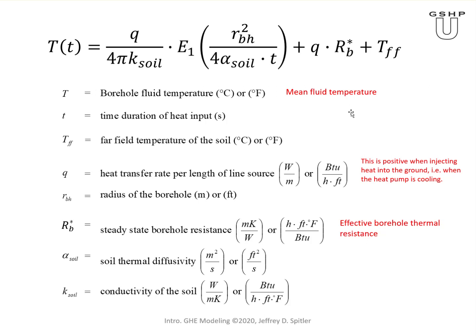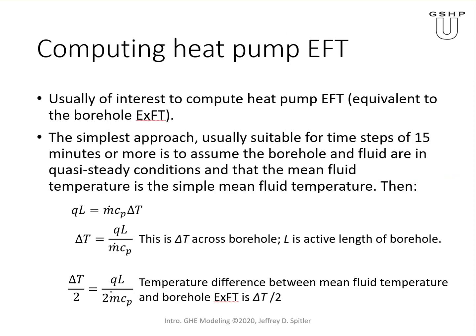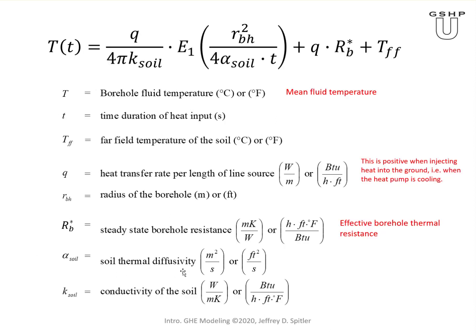T is the time duration of the heat input, so this expression is only valid for one fixed heat pulse — we'll get to how to use it when the heat input is changing. TFF is the far field temperature of the soil, also called the UGT, undisturbed ground temperature. Q is the heat transfer rate per unit length. RBH is the borehole radius, often abbreviated as little r sub B — distinct from capital R sub B, which is the borehole resistance. Finally, alpha and K are the soil thermal diffusivity and conductivity, respectively.